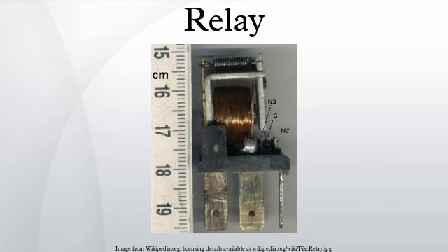Forced guided contacts are also known as positive guided contacts, captive contacts, locked contacts, mechanically linked contacts, or safety relays. Overload protection relay. Electric motors need overcurrent protection to prevent damage from overloading the motor, or to protect against short circuits in connecting cables or internal faults in the motor windings. The overload sensing devices are a form of heat-operated relay where a coil heats a bimetallic strip, or where a solder pot melts, releasing a spring to operate auxiliary contacts. These auxiliary contacts are in series with the coil. If the overload senses excess current in the load, the coil is de-energized. This thermal protection operates relatively slowly, allowing the motor to draw higher starting currents before the protection relay will trip.